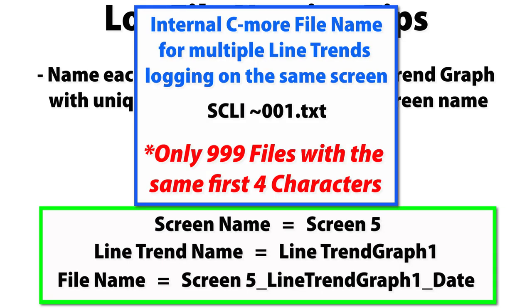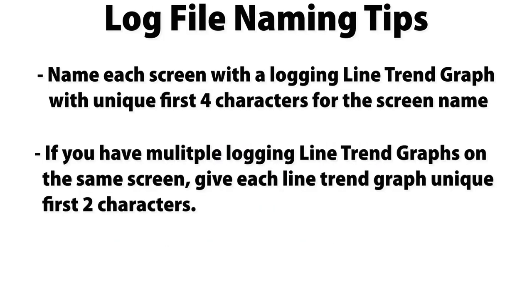If you do have multiple line trend graphs logging on the same screen, the internal file name will be the first two letters of the screen and the next two letters will come from the line trend graph name. Just make sure that the line trend graph name has unique first two characters.